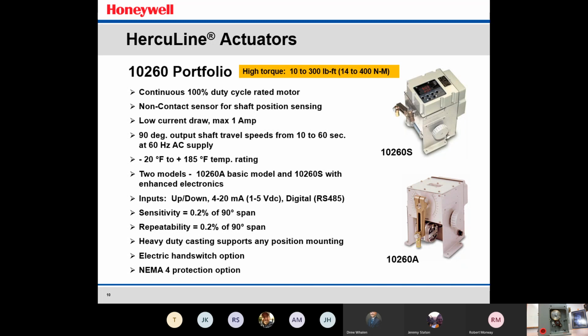If you would have had this actuator out in the plant 10, 15, maybe even 20 years ago, they would have had a slide wire that fed that position back to the control system. And on the old slide wires, those would become dirty. You'd have to clean them every once in a while. A lot of times the slide wire arm would break, and then it would cause very erratic control or even feedback signal to the control system. So on the new actuators with the non-contact sensing, it eliminates all those headaches, and you don't have to worry about the maintenance to go in there and replace those contact positioners.